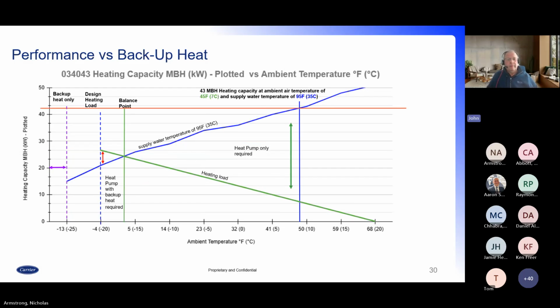So if you're at a point where you want to use a heat pump more often and not use the backup heat, of course, you're going to have to get a bigger heat pump. And this bigger heat pump, the next size up from the 28, is the 43. And you can see from the chart right away, the balance point has shifted to a much lower temperature now for outside temperatures. And now you can use that heat pump with the same design load, where we haven't changed our design output heat load. It's the same. We've just upsized the heat pump, and our balance point has shifted over, making a much more narrow margin of when you're going to use your backup heat.